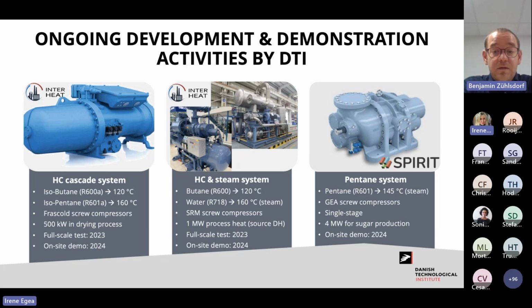And then finally, this is a pentane system, which we are developing as part of the Spirit project. It's together with GEA screw compressors. It will be providing steam at 140, 145 degrees. And this is a 4 megawatt installation for sugar production in Belgium on one compressor. And we're going for full-scale demonstration in '24 directly on site. So this was an overview of what we do, and this fits very well with the overall picture as we see it.